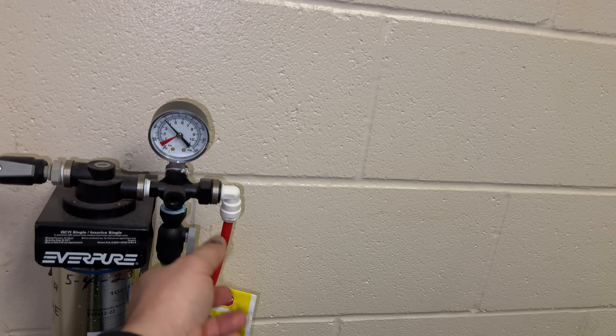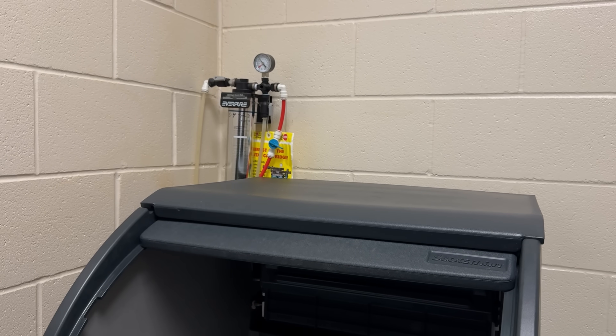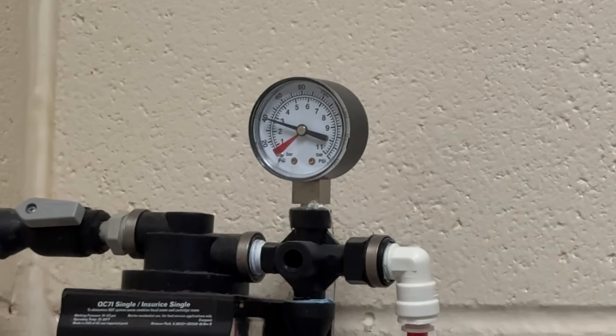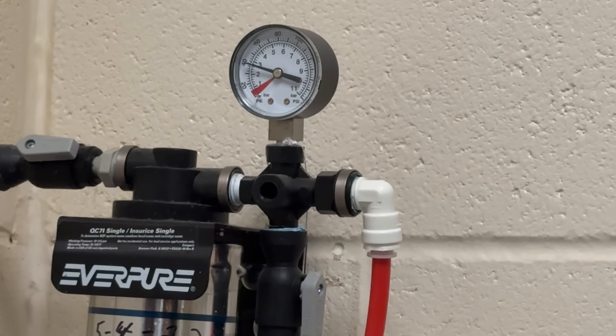This has a float — an electronic water float. It just went into harvest. Let's see what this thing does here. Water level at 40 right now. So you can tell it just drained some out, so it should be starting to fill up. You can hear the harvest cycle trying to happen.